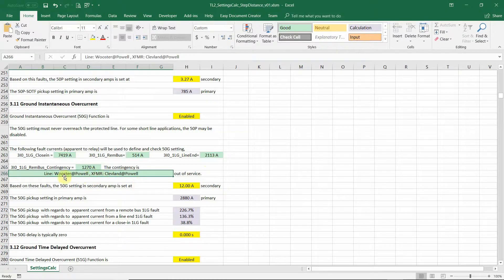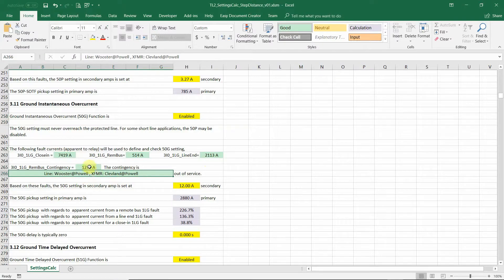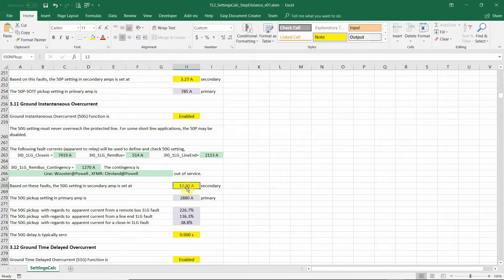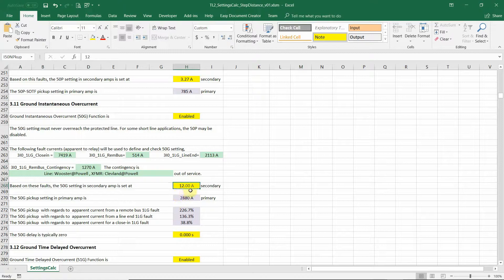And this one from a remote bus ground fault and a single contingency. It shows this contingency line and the transformer out of service for external fault. You will see this current. So the automated setting is 12 amp. And let's try to balance the sensitivity and security. But you can make a change.